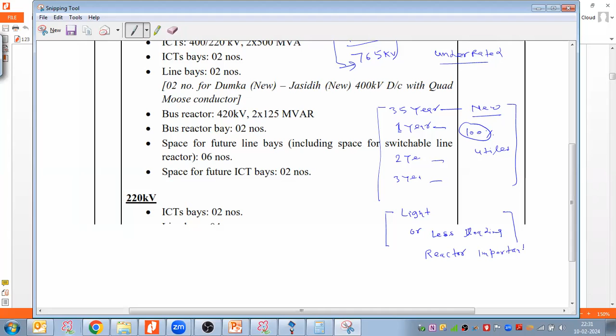But later on, when this substation is operated at 80% or 100% capacity, then we can switch off this reactor, or take it out of service. So for that purpose, when we connect a reactor, we connect it using a particular circuit with a dedicated breaker, CT, and disconnector, so whenever required we can isolate, switch in, or switch out. In the early days we keep it in service, in the switched-in condition.